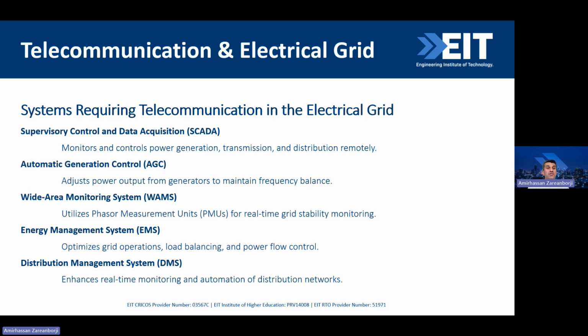Another system we use is the wide area monitoring system, or WAMS. They utilize phasor measurement units, or PMUs, for real-time grid stability monitoring. Based on the phasor or PMU, it will monitor how stable the network is. For example, if increasing the load by 1% or 2% will make the network unstable or not, or if decreasing the generation by 2%, 3%, or 5% makes the network unstable or not. It works on the stability of the system.